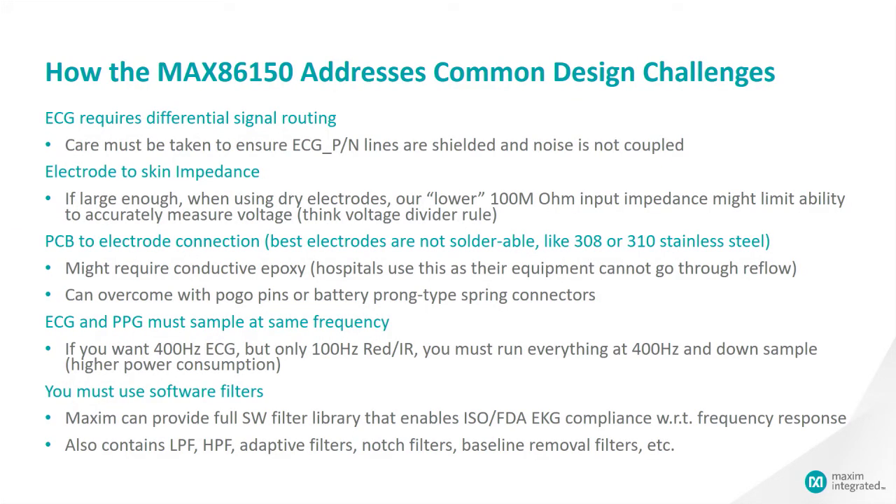So how does this part address the design challenges mentioned earlier? For the differential signal routing, you have to ensure the ECG P/N lines are shielded, which is simple. For the impedance at the contact point of skin and electrode, you have to try to stay above 100 megaohm input impedance for reliable measurements. We recommend conductive epoxy for PCB to electrode connection. Regarding the requirement for PPG and ECG to sample at the same rate, you may choose 400 Hz sample rate for both ECG and LEDs, though you only require 100 Hz for RED and IR LEDs.